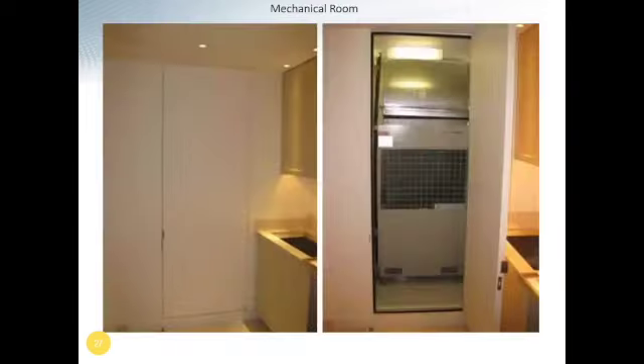Just to show another kind of application where this works, this is actually turning a small soffit in a kitchen into a makeshift mechanical room. As long as that soffit is going to be insulated and you're able to provide the same amount of makeup CFM that unit is exhausting, that is a completely acceptable application. There's very little need to provide a lot of service space around these units, especially if you're putting them inside, which makes installation extremely, extremely flexible.